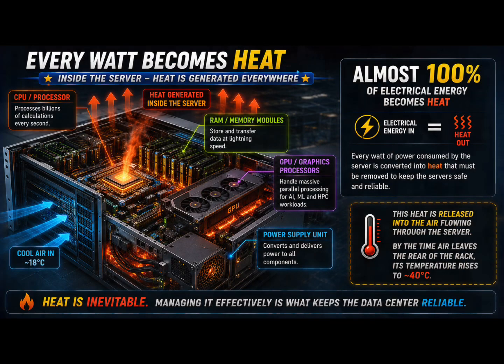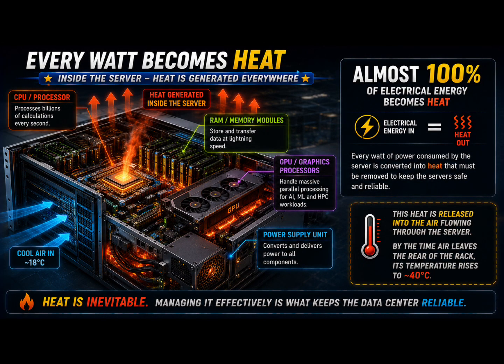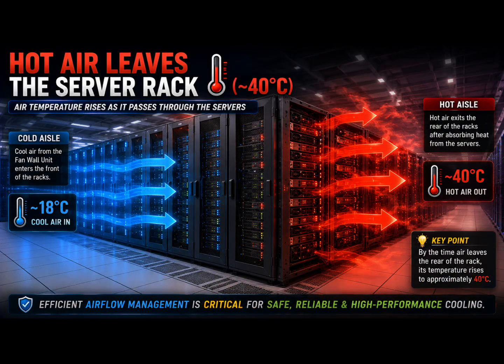It all begins inside the server. Every processor, every memory module, every graphics processor, and every power supply consumes electrical energy. And almost every watt of that electrical energy becomes heat. That heat is released into the air, flowing through the server. By the time the air leaves the rear of the rack, its temperature has increased to approximately 40 degrees Celsius.